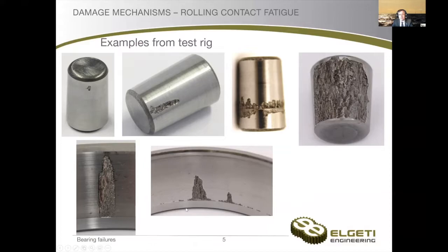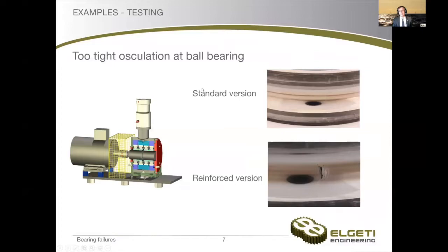Here, not again, because we have a different reason — we actually had some edge contact. What you can see here, the contact pattern was not good in this bearing, so we see plastic deformation. We have the first spalling still propagating in the axial direction, but then the failure did stop, simply because in this area we do not really have stress, and without stress there cannot be damage. Very simple. In real applications, it looks very similar — this is very characteristic.